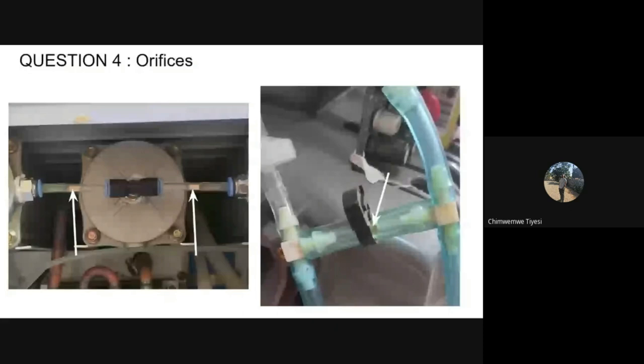A colleague recommends: if you have another current oxygen concentrator available, you can scavenge the tubing with orifices from that concentrator to replace the missing one. Linda adds that the graphic shows the tubing with orifices for the J5 oxygen concentrator on the left, and the tubing with the orifice fitting for the DeVilbiss 515 on the right.